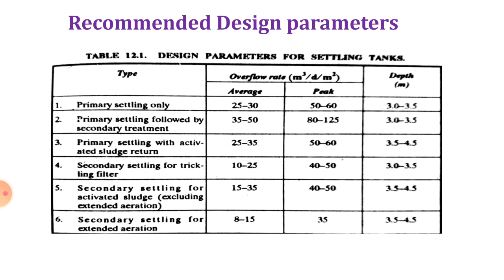These are some design recommendations or parameters to follow for the different types of settling. For primary settling, the overflow rate should be between 25 to 30 m³/day/m² for average and 50 to 60 for peak, and depth should be between 3 to 3.5 meters. As the type of settling changes, the overflow rate and depth vary accordingly. You have to refer to these parameters while designing the sedimentation tank as the case may be.